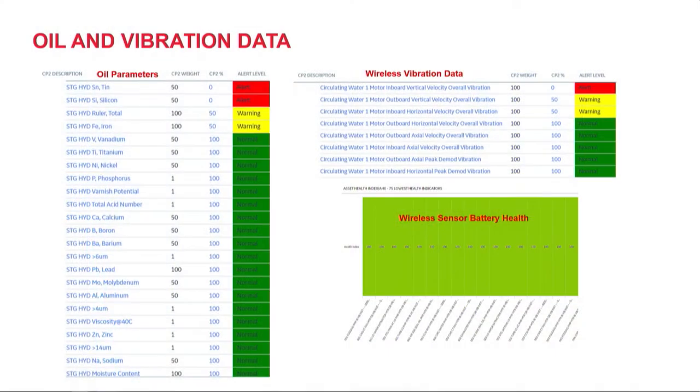One thing many of you may have experienced if you're trying to install wireless instrumentation is there's a lot of skepticism. Our I&C techs are used to wired, reliable instrumentation, and the idea of implementing wireless technology is not popular. It's really come a long way and we've been trying to prove that to people. These wireless sensors bring back battery health as a data point, so we bring that into Pi and created a dashboard for them to see all wireless sensors in the field and their battery health, providing warning if batteries are starting to decline. So far after a year, collecting data at a 10-minute interval, all of our batteries are 75% or above — we've seen some pretty good results.